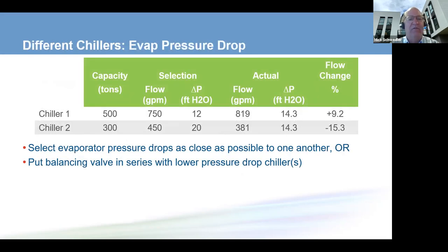This is an example of two chillers with different evaporator pressure drops. So a lot of times people say, well, here are my chiller capacities, here are my flow rates, and here are my pressure drops. The problem is that the water is smart. Water flows from high pressure to lower pressure. When both chillers are operating, the pressure drop across the evaporator bundles will be identical, because the flow rate through the chiller with a lower pressure drop will go up and the chiller with a higher pressure drop selection will go down until they become equal. So we get a discrepancy in the flow rates.